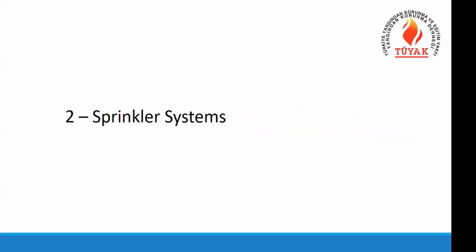So we will talk first about the widely used sprinkler systems in most of the buildings we have: in our schools, in the shopping centers that we cannot visit these days, or in libraries, in different types of buildings. We have always seen the sprinkler systems. These are also fire detection and fire extinguishing devices in one. So it's an automatic device that senses the heat coming from the fire, and it operates and extinguishes or controls the fire. So how does a sprinkler system work?